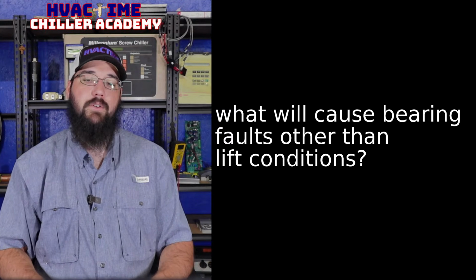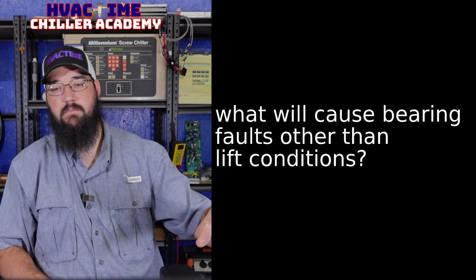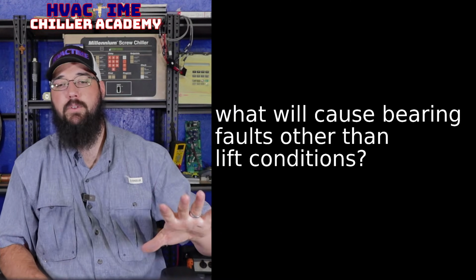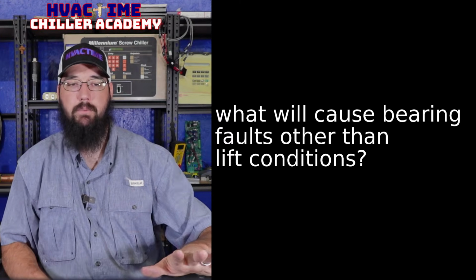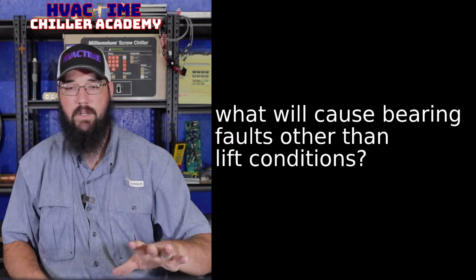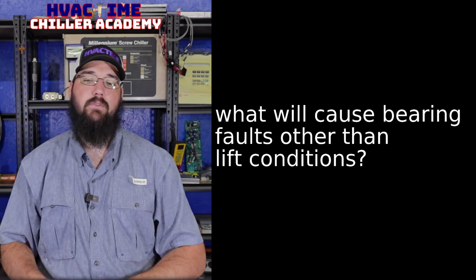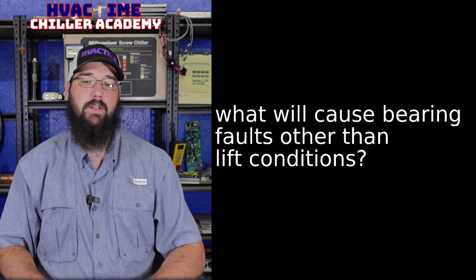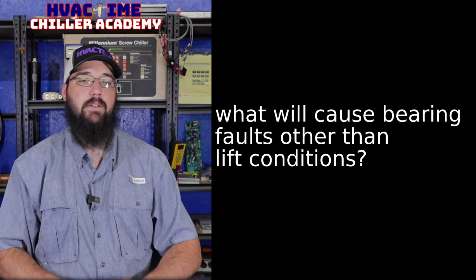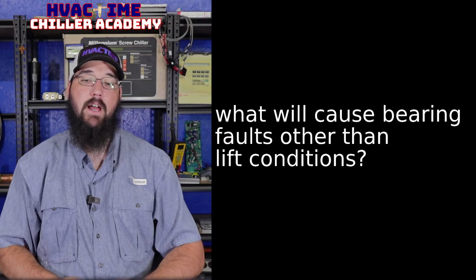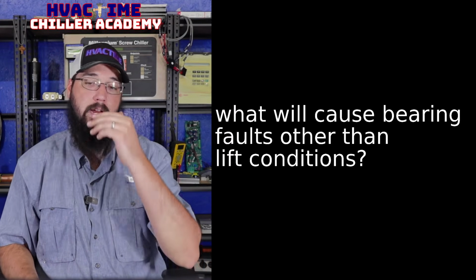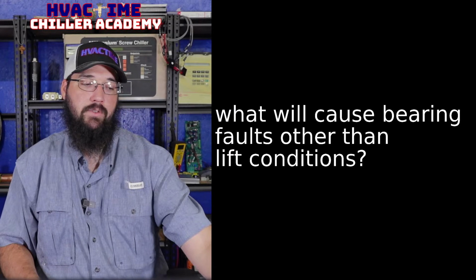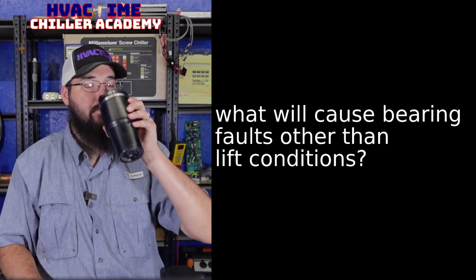So what are your superheats doing beyond just, I'm not arguing with you on lift, right? You say we don't have lift issues. I got it. What about superheat? What are your superheats doing when the compressor is online or when the trip happens? So if you look back at the logs, what are your superheats showing in the logs?